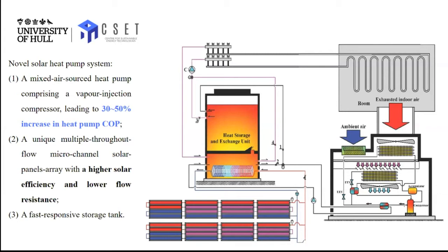By two-stage heat recovery, we can maximize heat recovery from the ventilation air. In the meantime, we make use of a vapour injection compressor, which can enhance the energy performance of the heat pump. By doing so, we would be able to achieve a 30 to 50% increase in heat pump COP. This is the second part of our technologies.